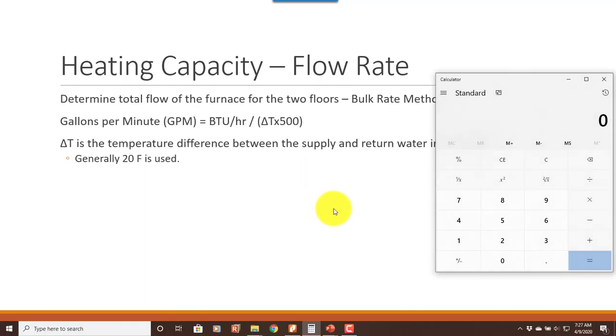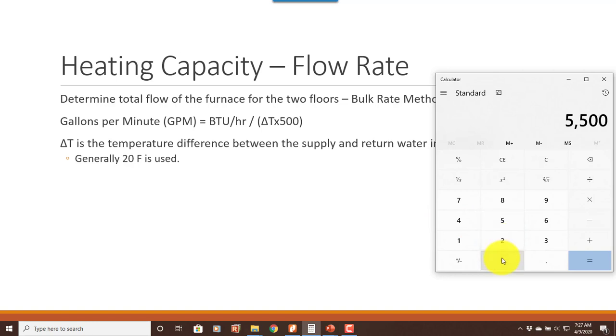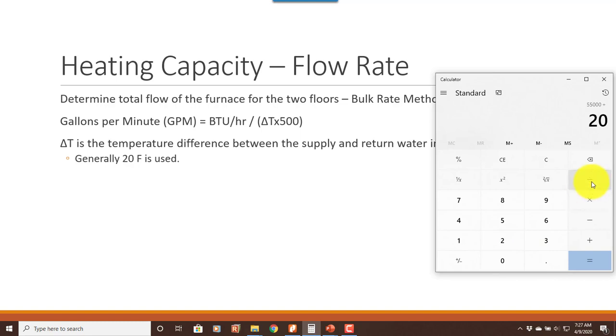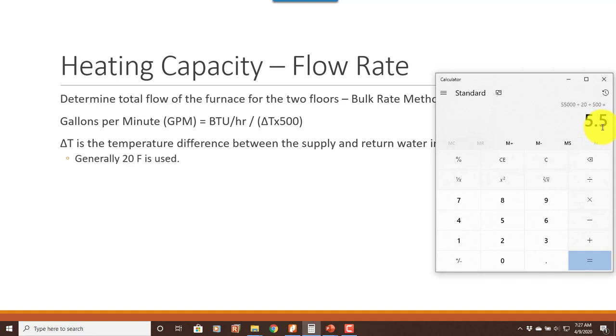Let me get to the calculator. We'll say our BTU per hour for this house is somewhere around 55,000. We divide that by 20 — the temperature drop — and then divide by 500, and we get about five and a half gallons per minute. So this is a very rough sizing of the boiler you need for the home — about five and a half gallons per minute — and that is probably about right.